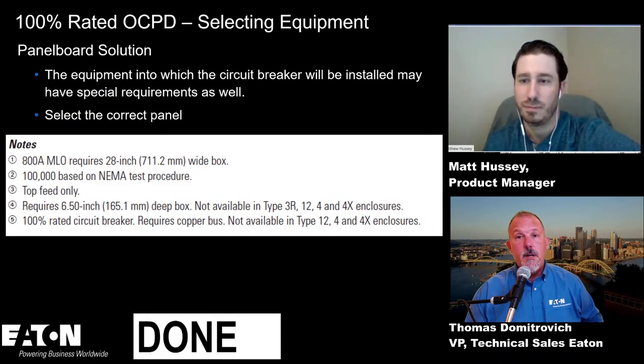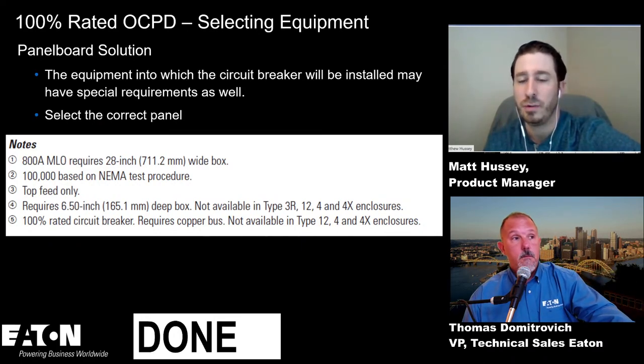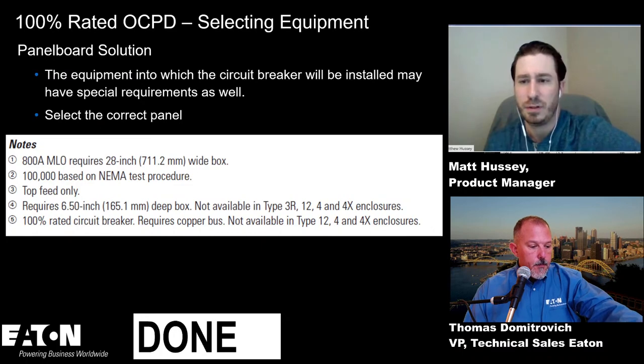Now you manage motor control centers. Do you have special 100% rated motor control centers, or are they all 100% rated? How do you handle that? Yeah, you'll see some specific differences within those constructions. Typically we rely on passive cooling, so you might see an increase in space or maybe additional ventilation, really as an effort to balance out the equation where the load that we're feeding is going to have a decrease in the cabling size. So now we have a more concentrated piece of that temperature within the compartment.